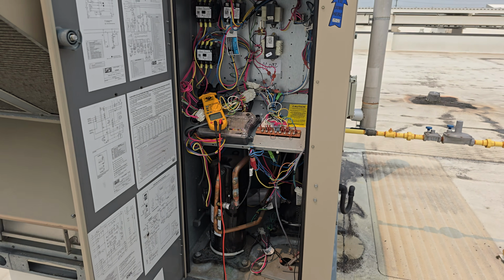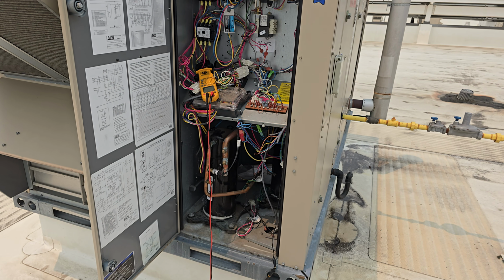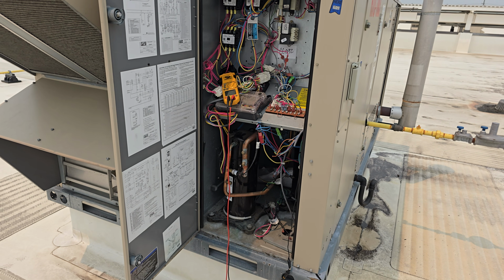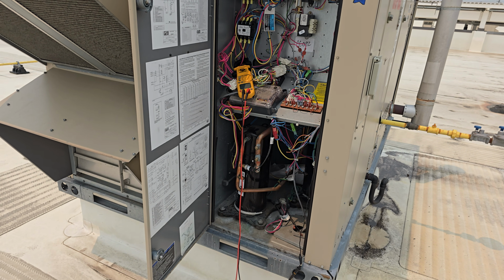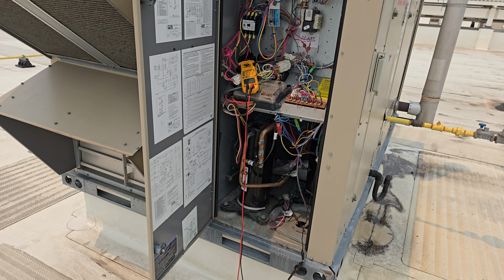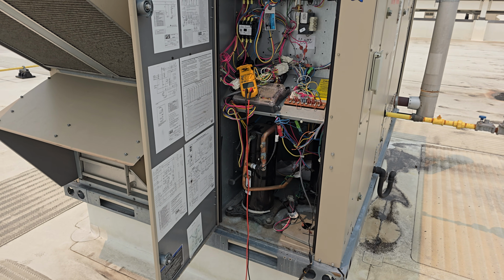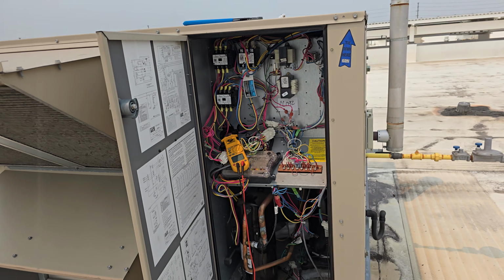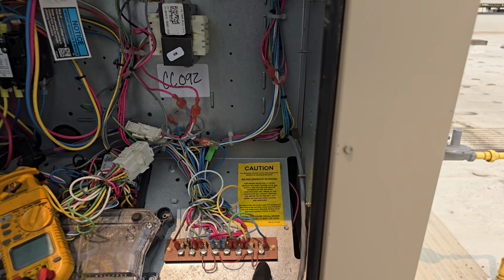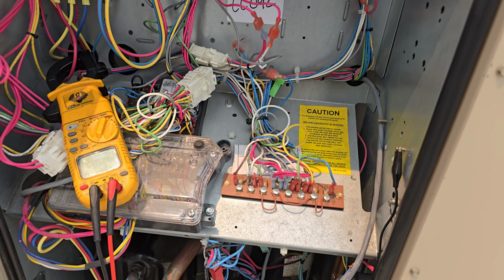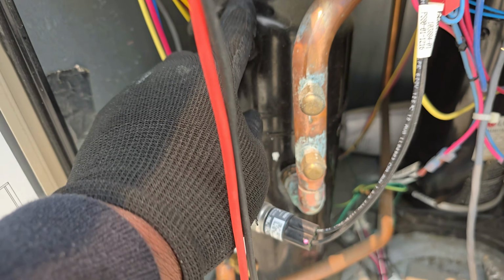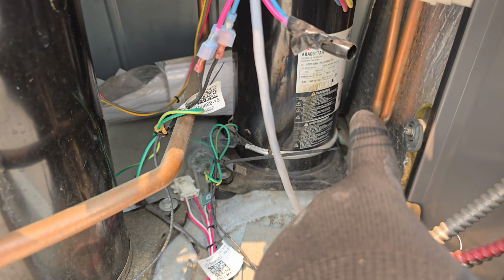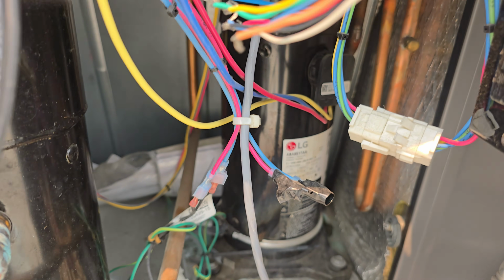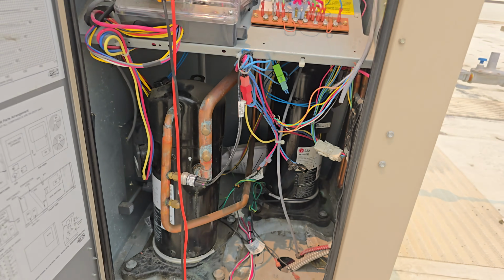If it's tripping off on the main electrical, then I would say, yeah, maybe the compressor. So I'm not going to rule out that the compressor is not the problem for now, but I want to check my low voltage. So I'm going to disconnect my Y2, which is compressor number 2. This is my compressor number 2. That's my compressor number 1 in there. There are 2 compressors in here.